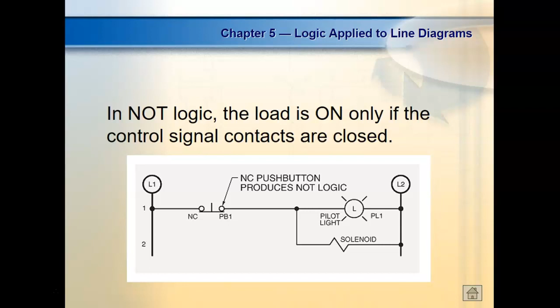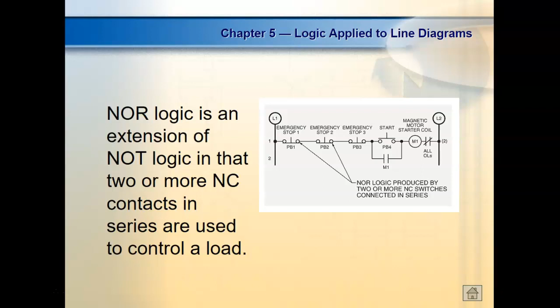Then you have NOR logic. This would be multiple e-stops. Why? Maybe we need an e-stop not just on one section, like our assembly line over here. Any one of those e-stops will stop that line. Any single one of them, whether it's the section for the robot or any assembly section, will stop the line. Why? Maybe I've got a collision somewhere, or something's gone funky and needs to be fixed. That is NOR logic.